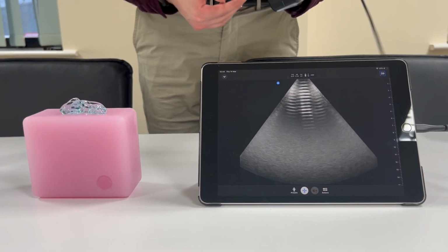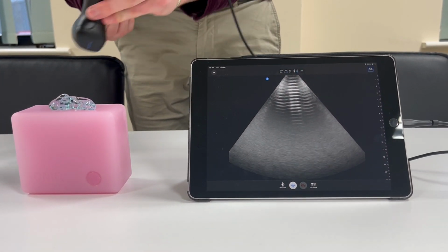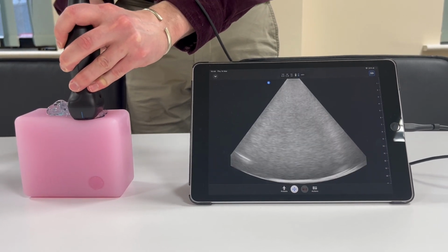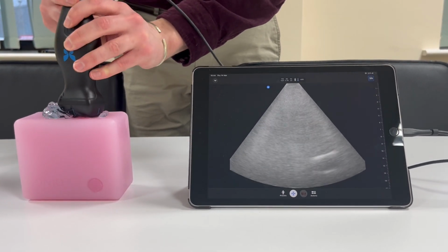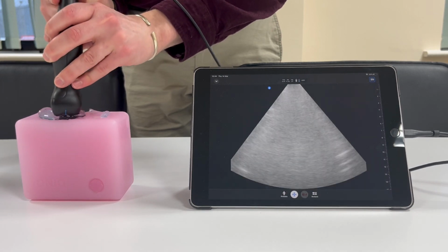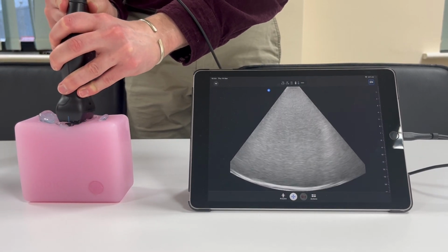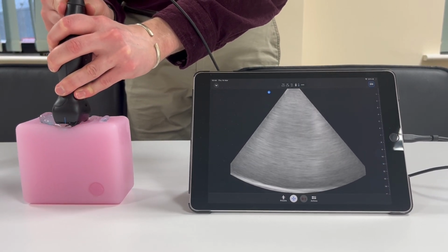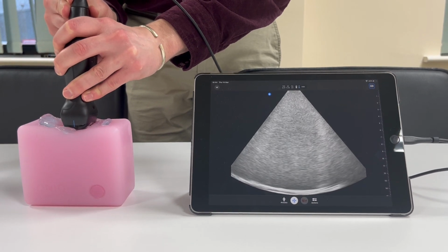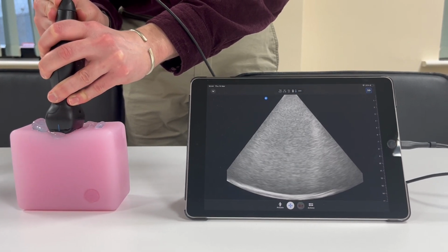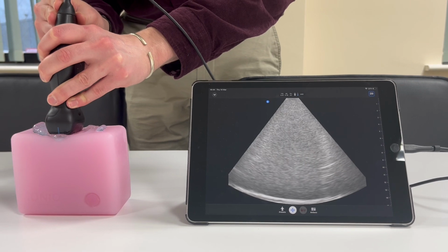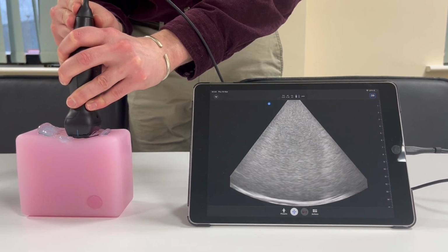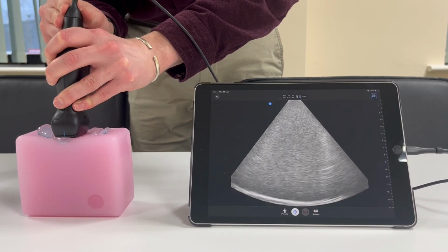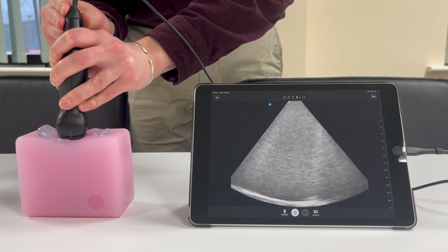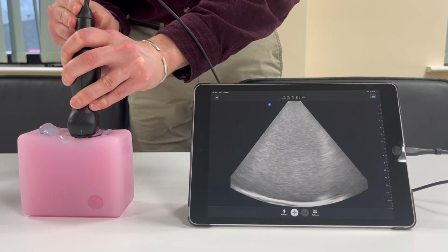When ready to scan, take your ultrasound probe and press it firmly into the surface of the phantom. Spread the gel evenly, and this should generate a uniform image. Any non-uniformities will show signs of transducer damage or damaged cables or any other faults within your ultrasound system.